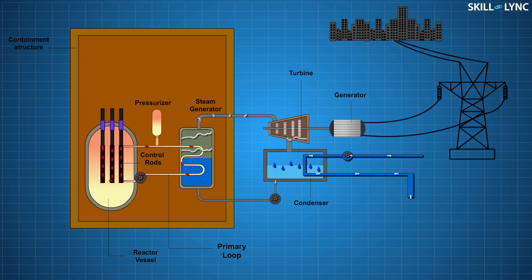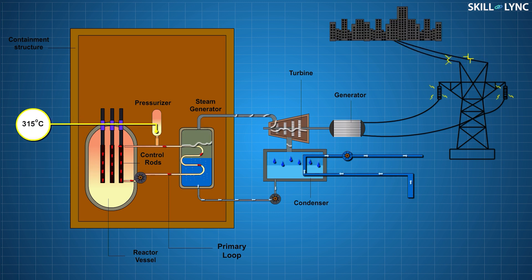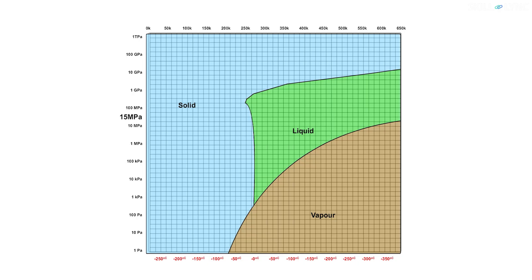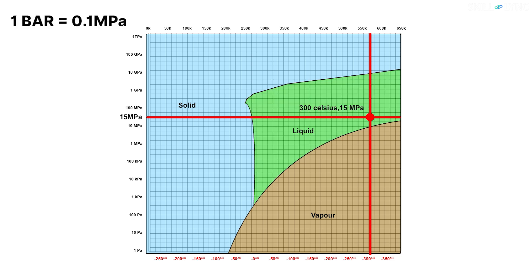In the primary coolant loop, demineralized water is used as a coolant. The temperature of water while entering the reactor core is around 275 degrees Celsius and increases to 315 degrees Celsius as the water is heated. Despite having high temperatures, water in the loop remains in the liquid state, because the pressure in the loop is usually around 155 bar, which corresponds to the liquid phase in the phase diagram shown.